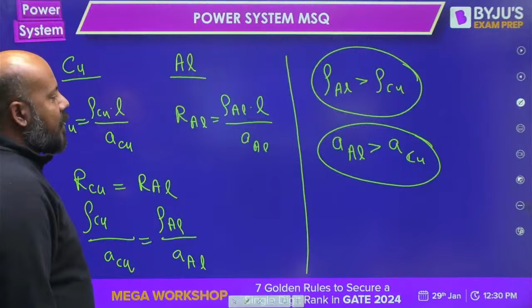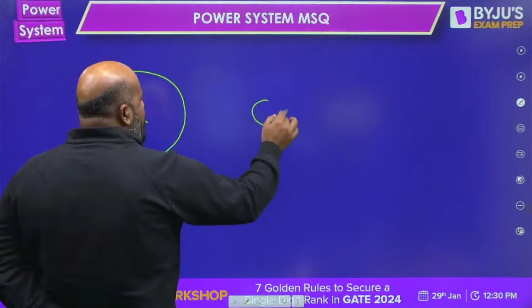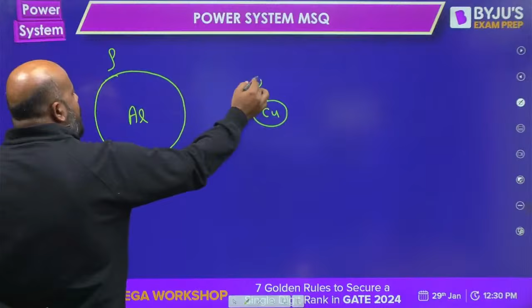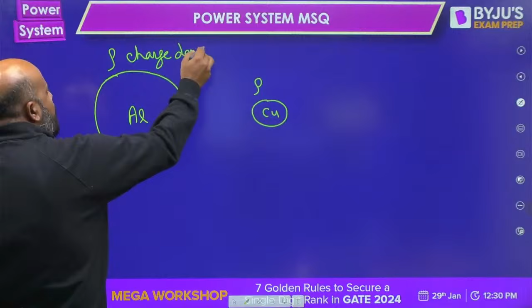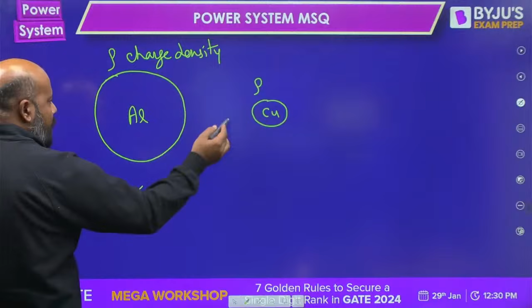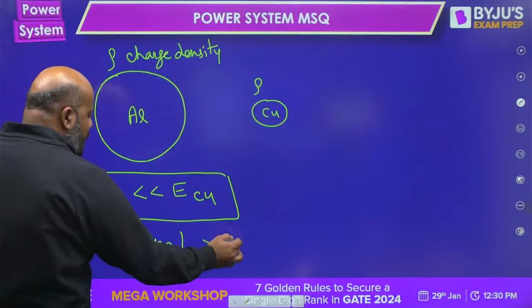Now understand, if the cross section area is more, suppose this is your aluminum conductor and this is your copper conductor for same resistance. For same charge density, not resistivity, if you find the electric field stress at the surface of aluminum is less compared to the electric field stress at the surface of the copper conductor, that is the reason the possibility and intensity of corona in the copper conductor is higher compared to the aluminum conductor. Is it clear, everybody?